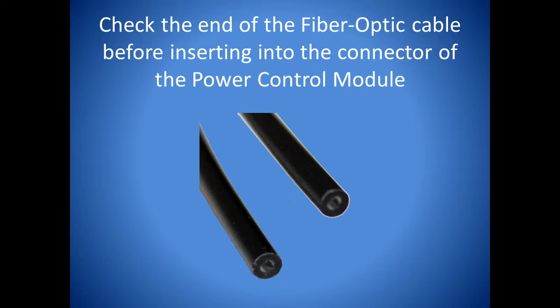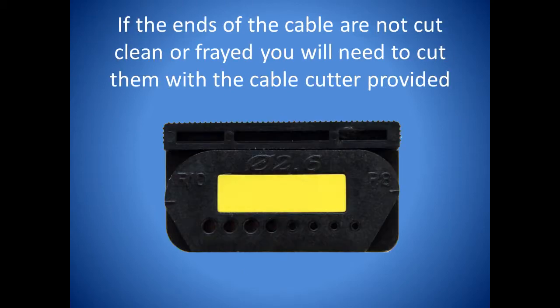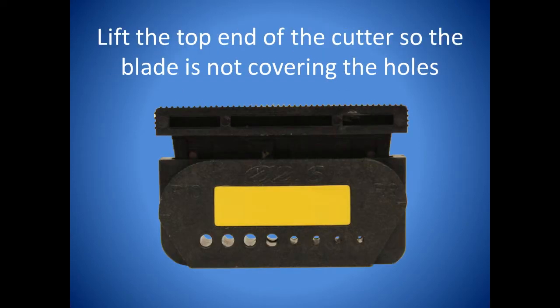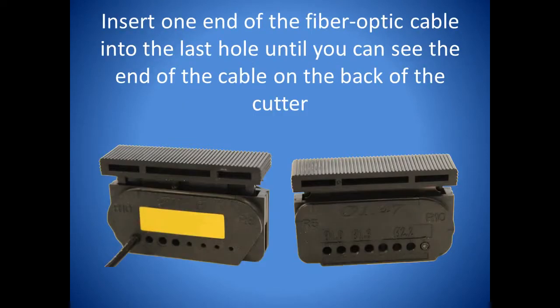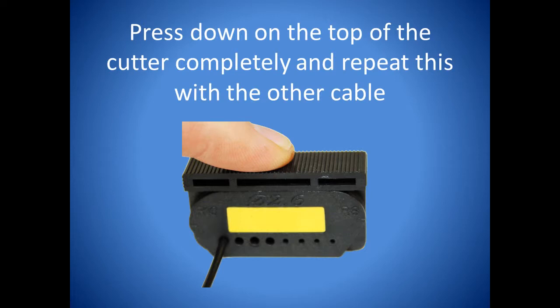Check the end of the fiber optic cable before inserting it into the connector of the power control module. If the ends of the cable are not cut clean or are frayed, you will need to cut them with the cable cutter provided. To cut the ends of the cable, lift the top end of the cutter so that the blades are not covering the holes. Insert one end of the fiber optic cable into the last hole until you can see the end of the cable on the back of the cutter. Press down on the top of the cutter completely and repeat this with the other cable.